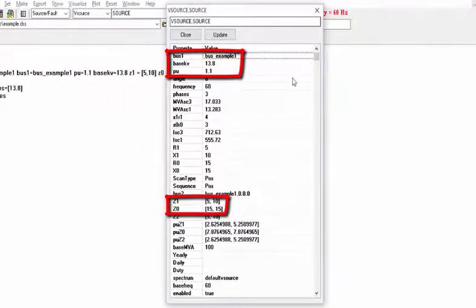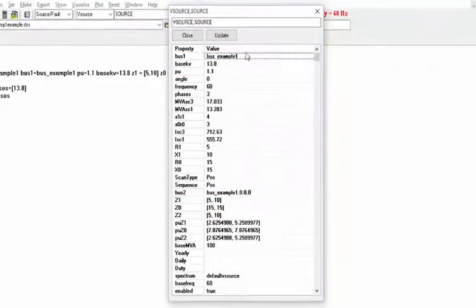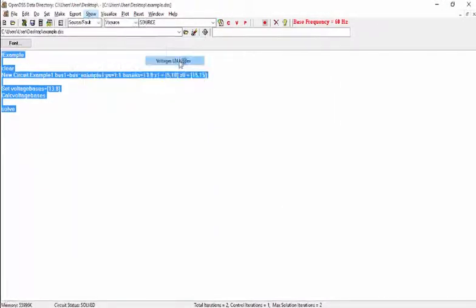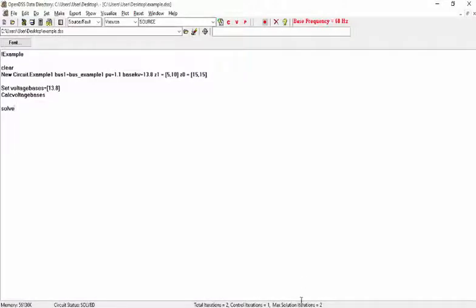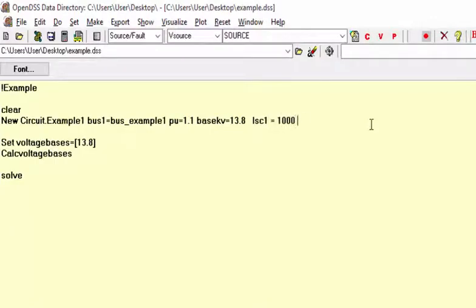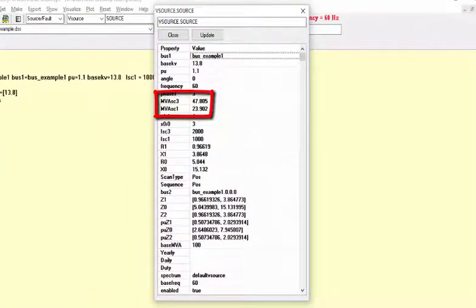As you can see, all of them are matching with what we have defined. The values of the pair MVASC3, MVASC1, and ISC3, ISC1 were calculated based on Z0 and Z1 that we have defined. If we go to show and line-to-neutral voltage, we can see that the actual voltages are in accordance with the PU value of 1.1 that we have defined. You can also use ISC1 and ISC3 instead of Z1 and Z0. Let's set ISC1 equal to 1000 and ISC3 equal to 2000, for example.